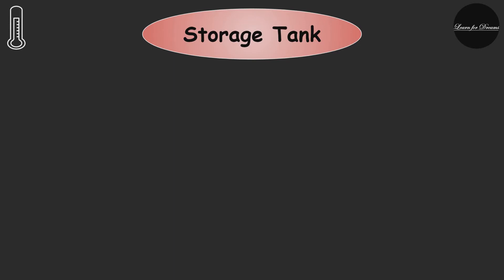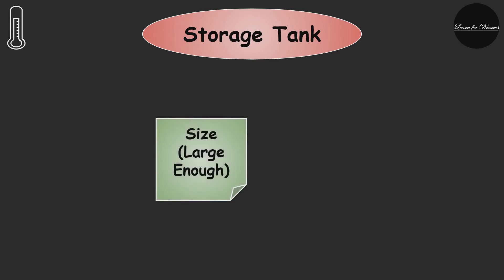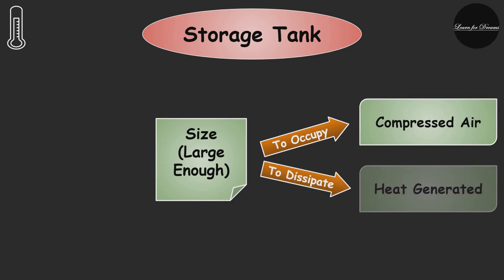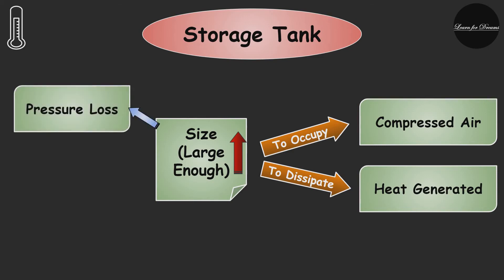The compressed air coming from the compressor is stored in a storage tank, which is a very important part of a pneumatic system. The size of the storage tank should be large enough to occupy the compressed air. It also helps to dissipate the heat generated. The pressure in the storage tank is kept higher than the operating pressure of the system to compensate for the loss of pressure in the transmission system.